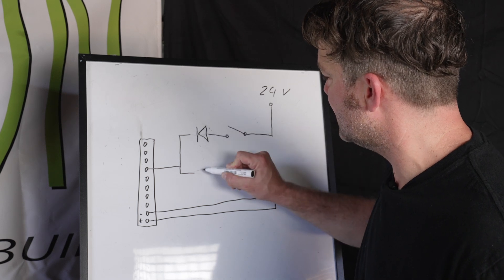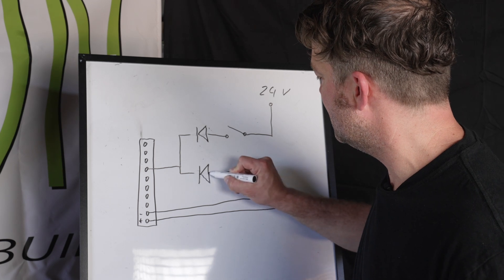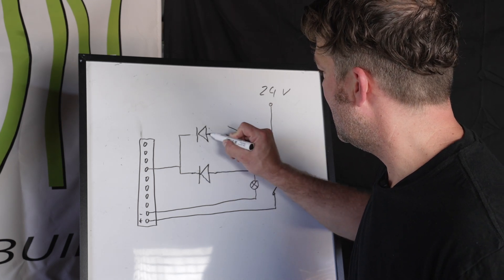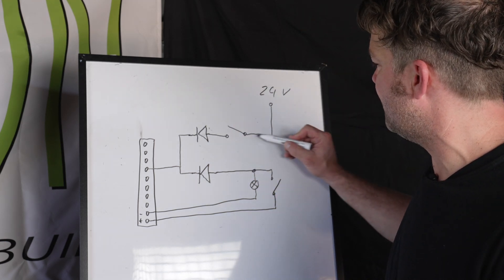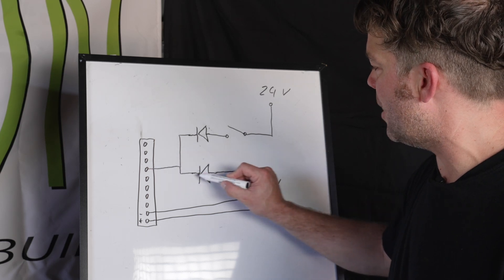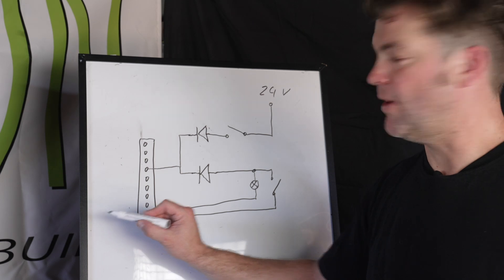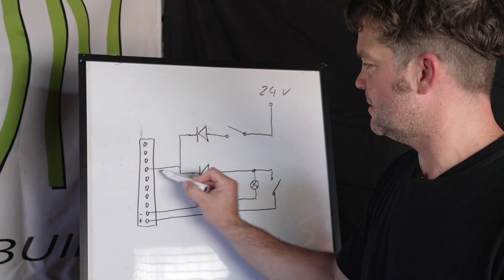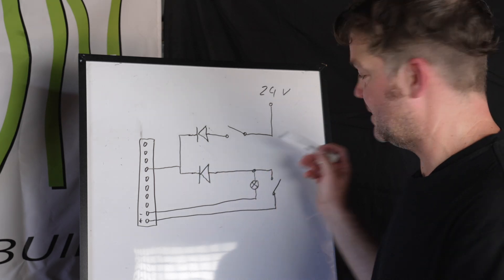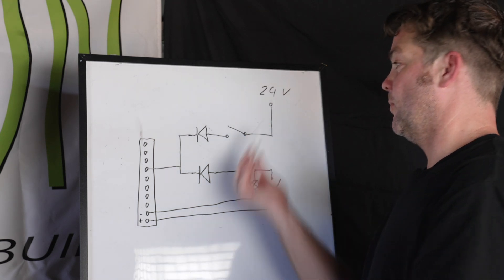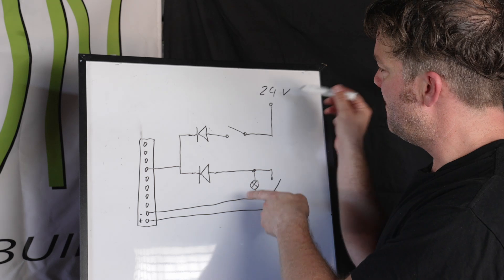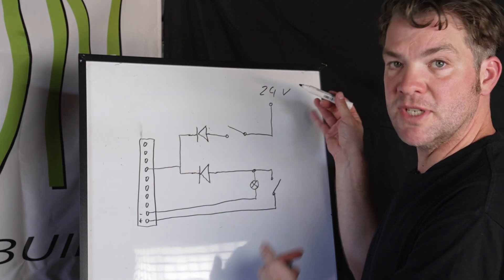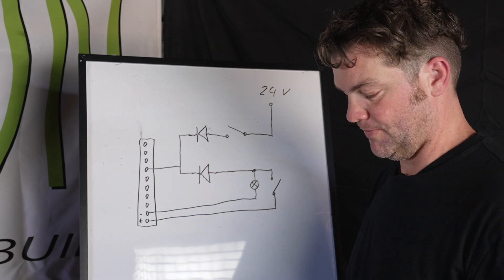What you will do is you can put blocking diodes in here. Three amp blocking diodes are plenty for this application. And if you put these in externally in this way, what you do is as soon as you got 24 volt power here, it will go to the circuit board, but it will not be able to run back to the 12 volt system. And vice versa, the 12 volt cannot go back to the 24 volt system, even though that wouldn't be possible anyway, because 12 and 24 won't go that way. It will only go this way. But this is how you can mix different voltage switches and systems to activate relays on the circuit board.